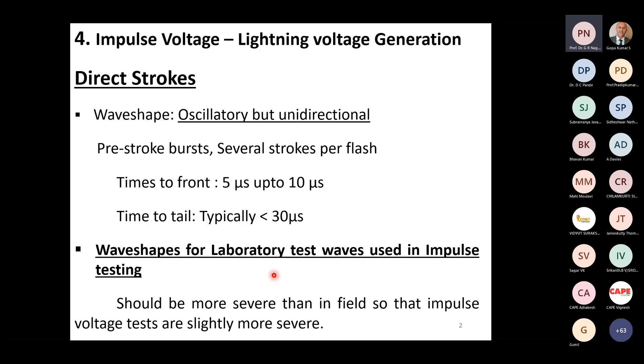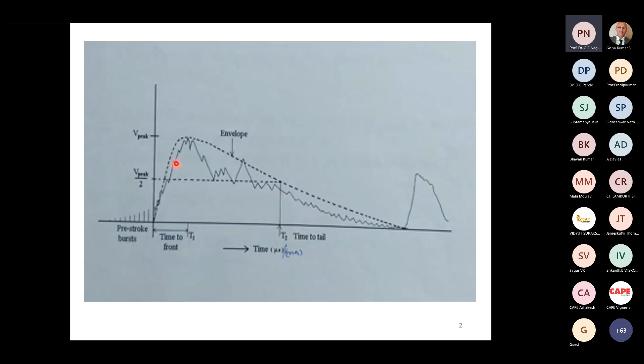So now, if you think of a lightning wave, you see this is the real final stroke. It can be oscillatory, like this tail, and then one more stroke like that. Now, these strokes occur before the main burst. These are known as the pre-stroke bursts. I have only told you time to front is the time from 0 to the peak value. Time to half value is like this, time to tail. The envelope gives us the shape, but the magnitudes and times to front we decide based on, as I told you, higher security concerns for the equipment under test.